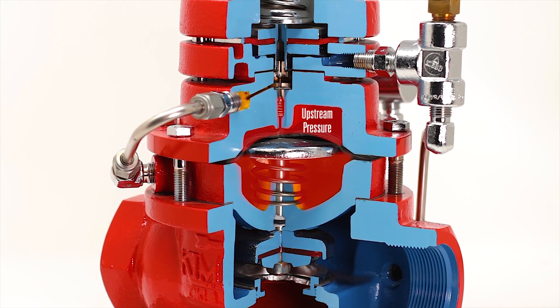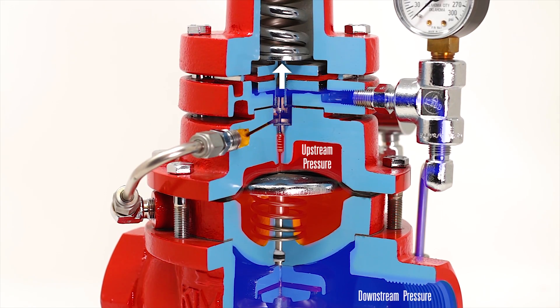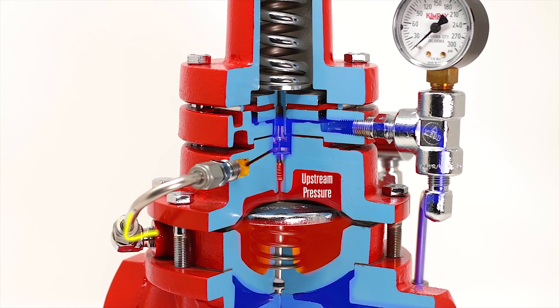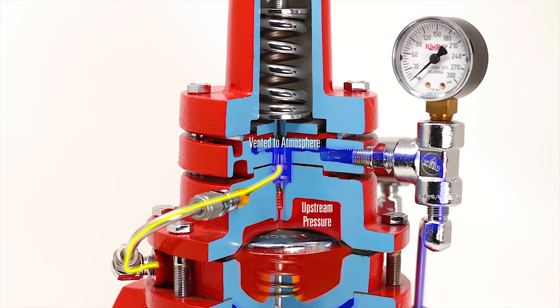If the set point is exceeded, the downstream pressure pushes up on the sensing diaphragm assembly closing off the pilot plug. This allows gas to be vented from underneath the motor valve diaphragm and the downstream pressure to be regulated.